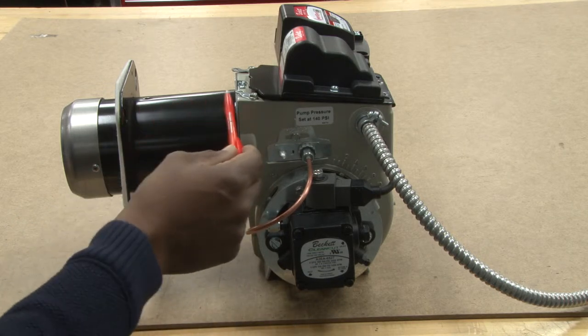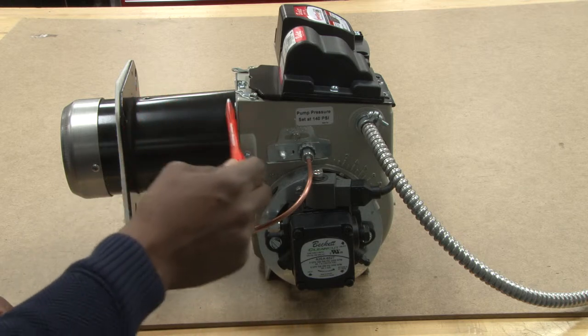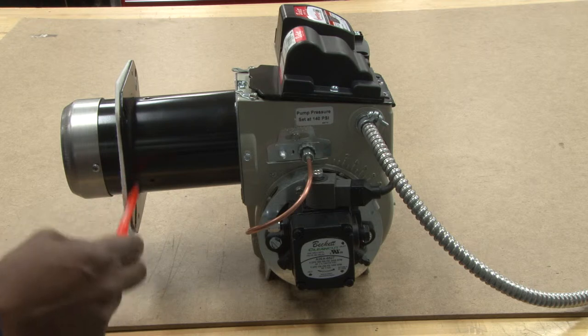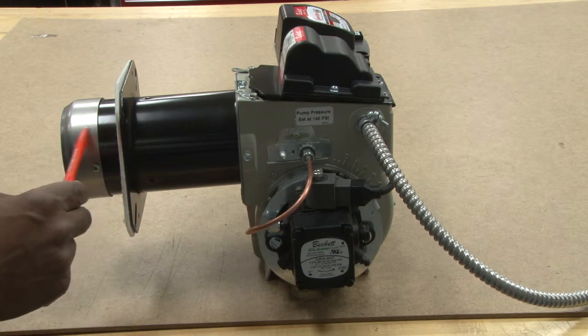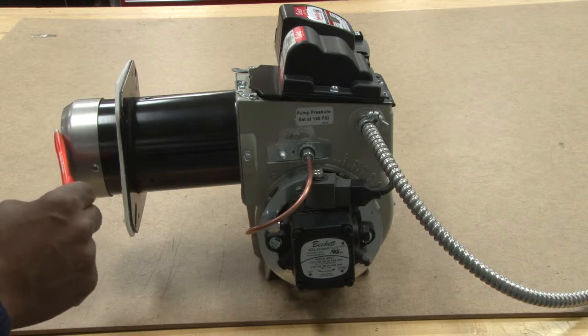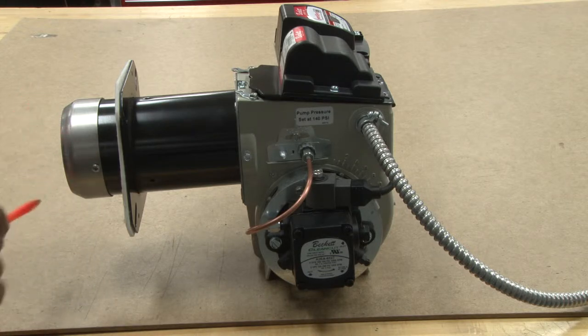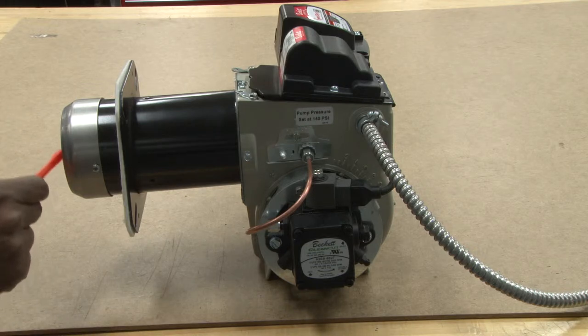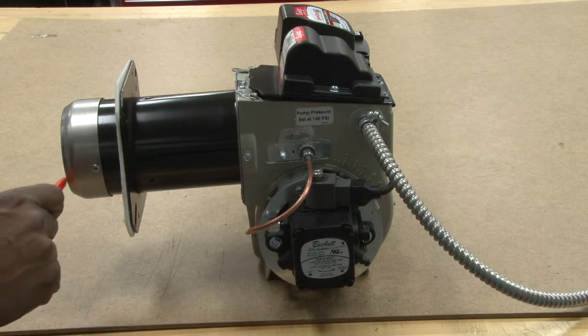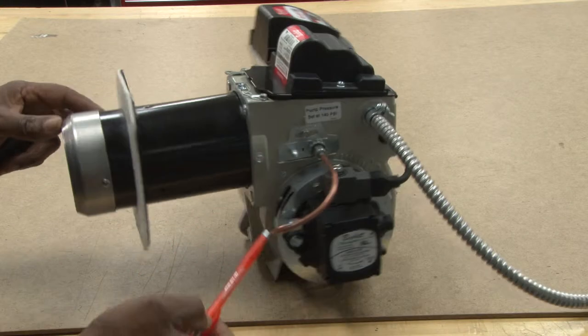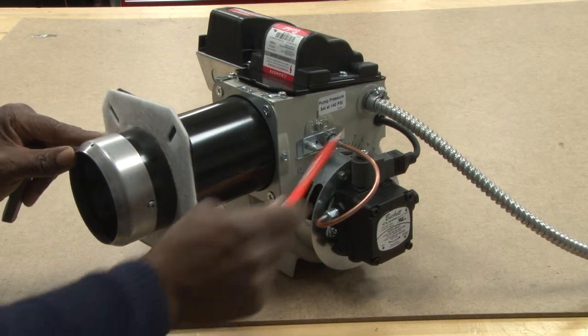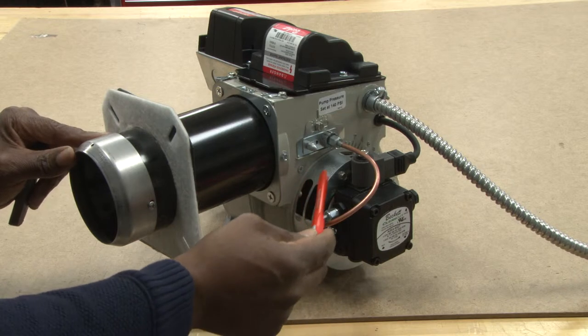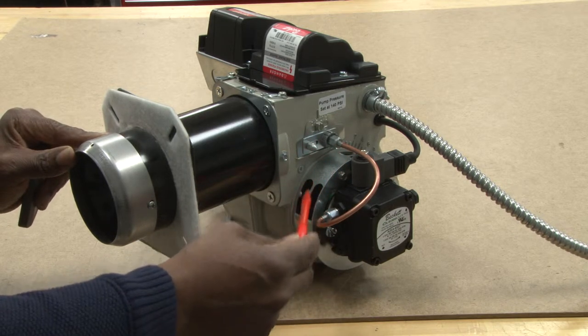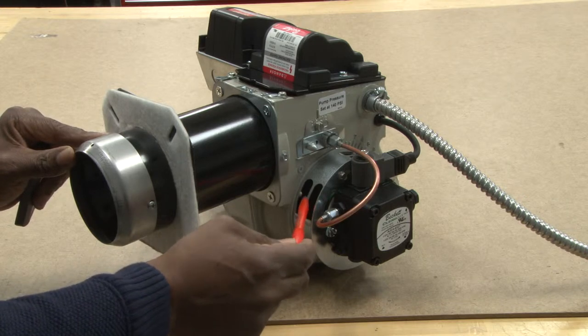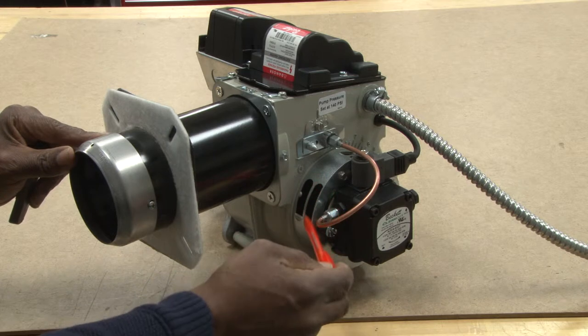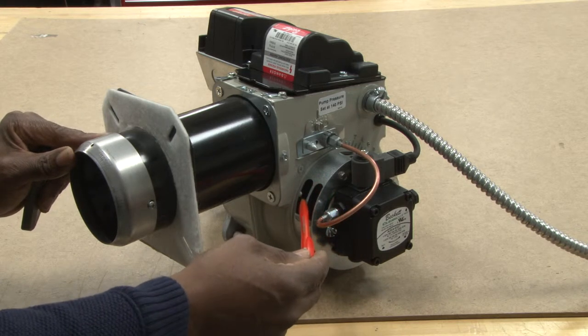And this is the burner tube, this portion is external of the furnace. And this plate, this flange, will be the portion that will be inside of the combustion chamber of the furnace. This will produce the flame outside of the burner to create heat inside of the combustion chamber. Other components here will be the air intakes. There will be multiple air intakes around this burner and an air shutter to adjust the amount of air mixture with the fuel burning. So by adjusting this, you can increase or decrease the amount of excess air for the burner.